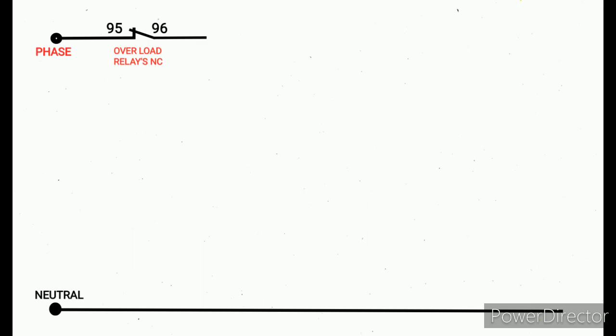Next step, that overload relay NC 95-96. This NC is used for overload tripping. If the motor gets overload, that overload gets tripped so that 95-96 NC comes to NO, so the circuit is protected. Next we need to draw off push button in series with that overload relay NC.